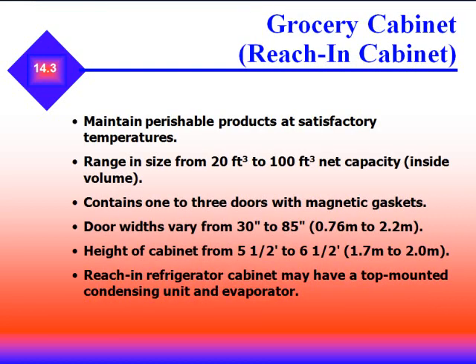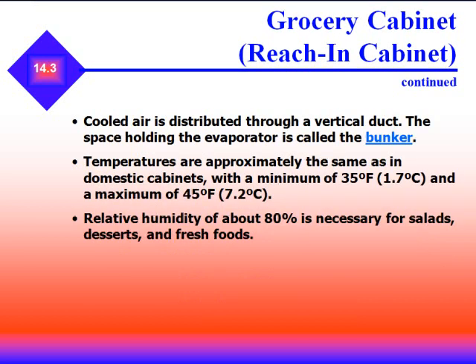Grocery cabinets are reach-in cabinets that maintain perishable products at satisfactory temperatures. They range in size from 20 to 100 cubic feet net capacity, contain one to three doors with magnetic gaskets, door widths varying from 30 to 85 inches, and heights from 5.5 to 6.5 feet. The reach-in refrigerator cabinet may have top-mounted condensing units and evaporators, with cooled air distributed through a vertical duct. The space holding the evaporator is called a bunker. Temperatures range from a minimum of 35°F to a maximum of 45°F, with relative humidity about 80% — necessary for salads, desserts, and other fresh foods not to dry out.